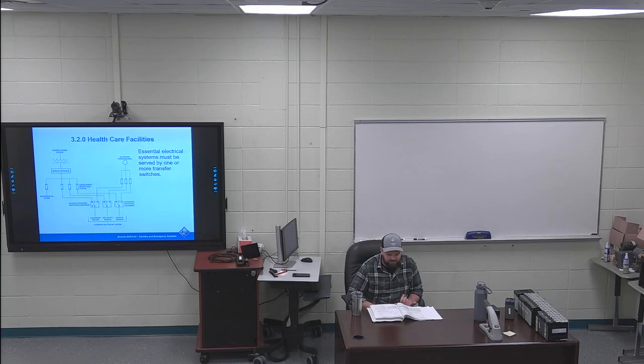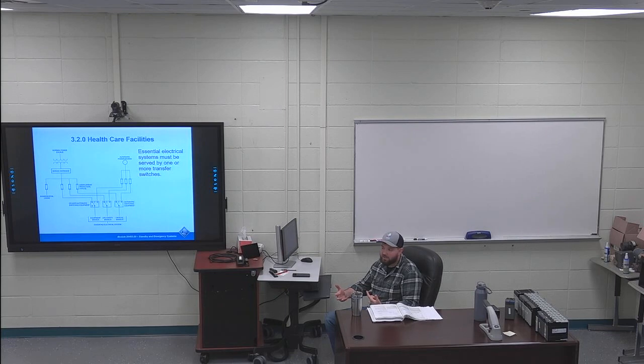But you also have to have exit signs, alarm and alerting systems, communication systems, generator set accessories, elevators, automatic doors. All that stuff has to be on emergency power, especially in the hospital. You think about, like, why on earth would you have to have an elevator on emergency power? You don't want to try to get somebody down the stairs in a wheelchair that has 0 help at all. Elevators have to be on emergency systems.